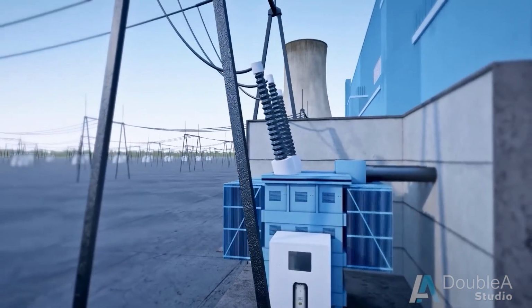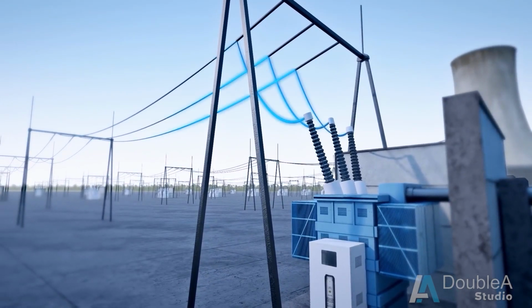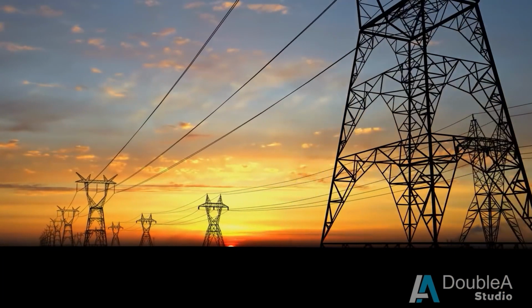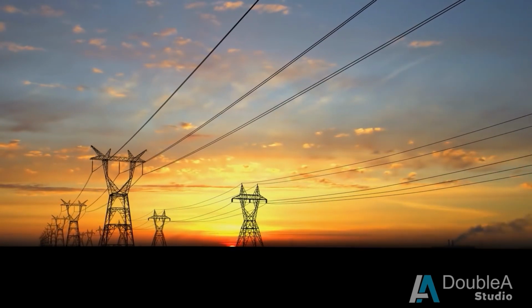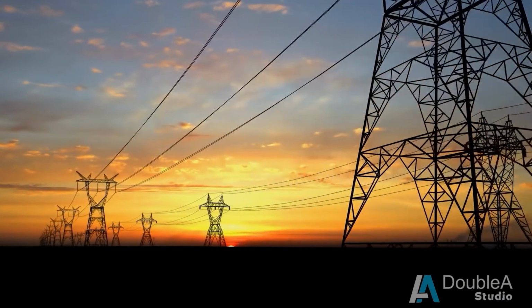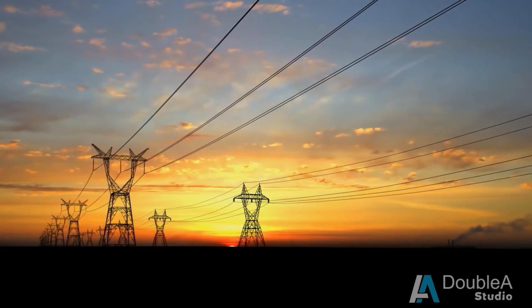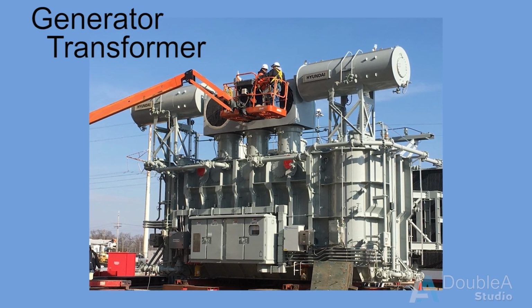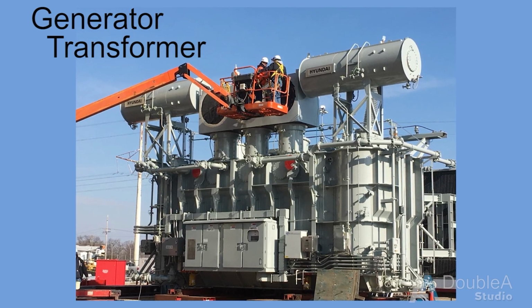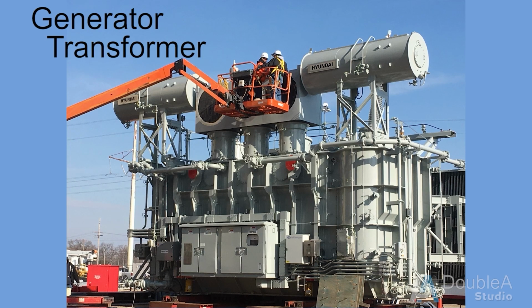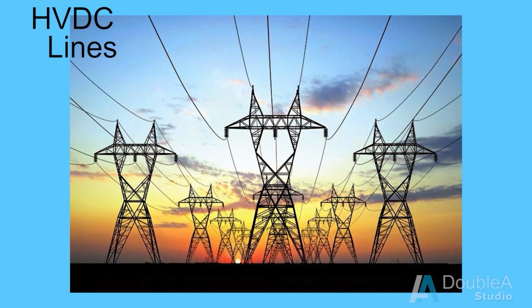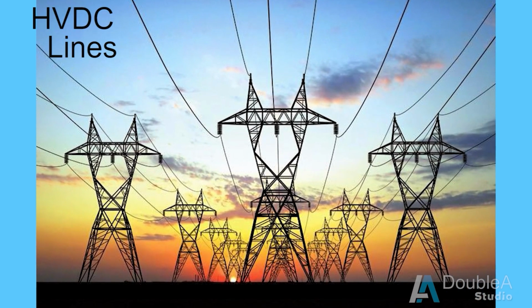Transmission is the bulk movement of electrical energy from a power station to an electrical substation close to the electricity consumers. The interconnected lines form a transmission network or power grid. When electricity is generated at a power station, it will typically be anywhere between 11 kilovolts and 33 kilovolts. It is then stepped up using a generator transformer to a voltage between 132 kilovolts to 765 kilovolts or more, depending on the distance of transmission. The longer the distance, the higher the voltage level. Generally, power is transmitted as high voltage, three-phase alternating current. However, high voltage direct current, say HVDC, technology is used for greater efficiency over very long distance transmission.